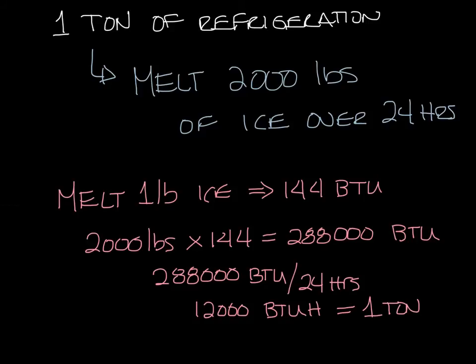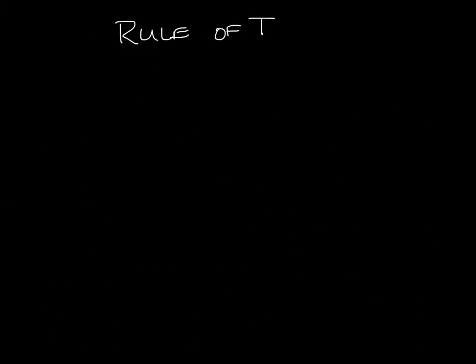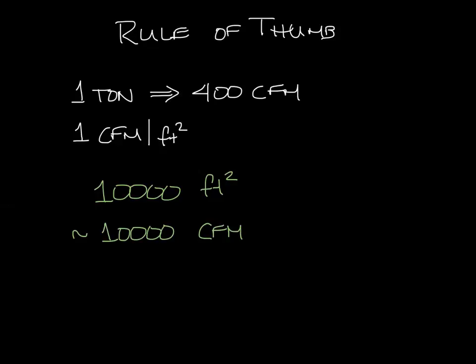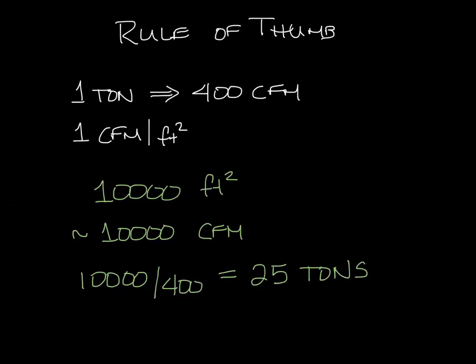Now let's cover a couple of handy rules of thumb. First, you'll want about 1 ton for every 400 CFM. And in a typical office you'll have about 1 CFM per square foot. So say you have a space that's 10,000 square feet — you know that'll be about 10,000 CFM. And if you divide that by 400 CFM per ton, you get 25 tons of refrigeration for that space. It's a handy rule of thumb.